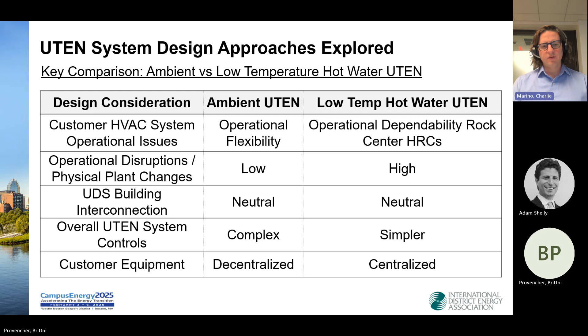On the next slide you'll see an overall diagram of what's happening with the UTEN system. The building 1-9 cooling towers, located at 30 Rock in Rockefeller Center, generate heat by displacing heat from the existing chillers. We tap into that condenser water loop and grab heat directly from the chiller. Once it's in our heat exchanger and displaced into the utility distribution system, we can pass it to the other individual buildings through a series of heat exchangers and hydronic loops.